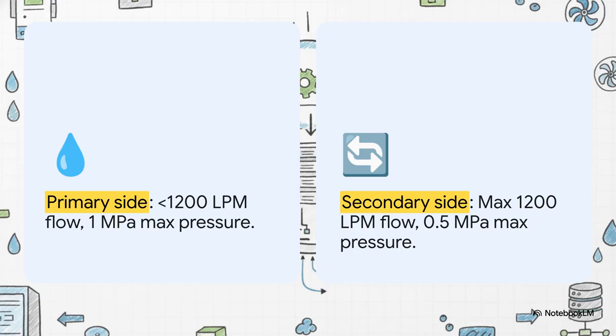Now compare that to the secondary side loop. This is the closed loop that actually runs into the server racks. It operates with a maximum flow rate of 1,200 liters per minute, but at a much lower maximum pressure of 0.5 megapascals. Both sides use 4-inch ANSI 150-pound flanges, which is crucial for handling these dense, high-volume connections safely.